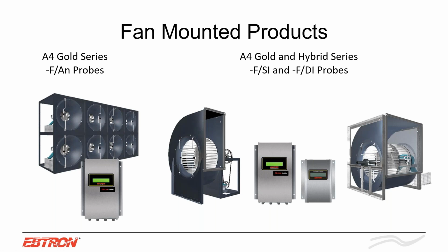We see a lot of piezo rings still, which is differential pressure. I'm not going to get into technology differences, but the one thing I will say is if you wanted a differential pressure piezo ring to perform the same as this, you have to specify a 0.1% pressure transducer in your spec, and you have to have a transducer on each individual one of these, because that's what we're doing. We're measuring at each individual fan. And again, our sensor accuracy is plus or minus 2%.